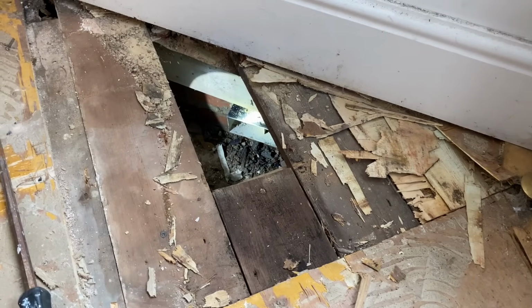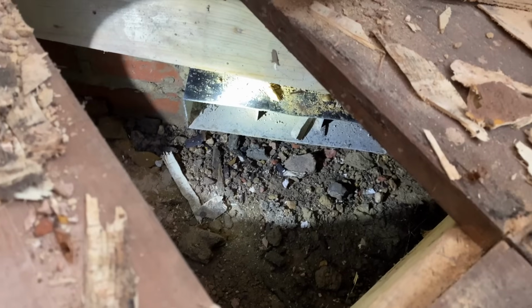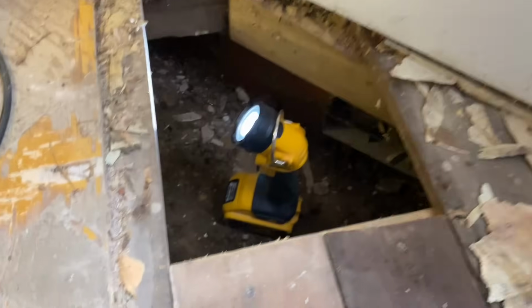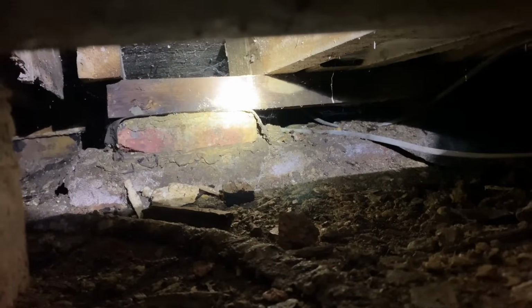When you're dealing with mechanically extracted air, so air that's forced, it's important that that air flows down a smooth, straight line as possible, because you're forcing the air. Every time you add a junction, so every time you add a bend, the flow rate becomes less. That's not the same when you've got passive air vents such as this, so any idea that they won't perform as well is not particularly true.